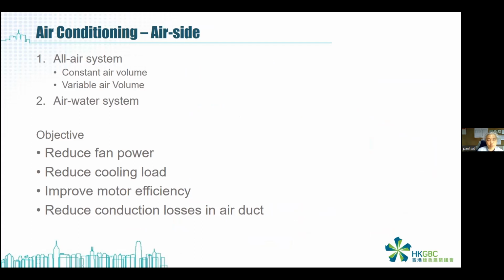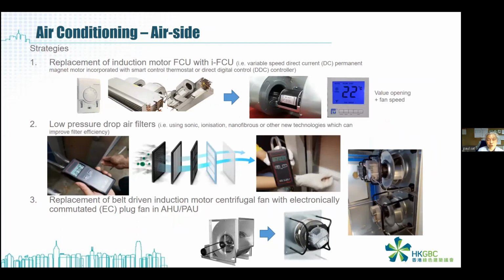And for the air side, we also have the constant air volume system, variable air volume systems, and also the air water system. Air water system means the fan coil unit system. The objective of this air side is to reduce the fan power and cooling load, increase the motor efficiency, and also reduce the air duct frictional loss. One thing is that we want to convert the conventional fan coil units, which use conventional mechanical or valve control, fan speed control, into what we call the iFan coil or smart fan coil unit system.